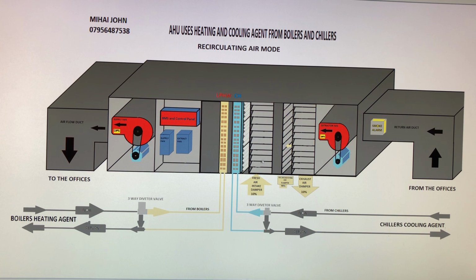So I will only open the damper 10% to suck in the minimum amount of air, just to overcome, as I said before, the CO2. The same quantity of air should be exhausted, taken out of the building through the exhaust air damper, and the recirculating damper will be 90% open, just to make sure I'm not losing too much energy from the building. Then the building management control will call for the chiller to run. So the chiller will be called to run.